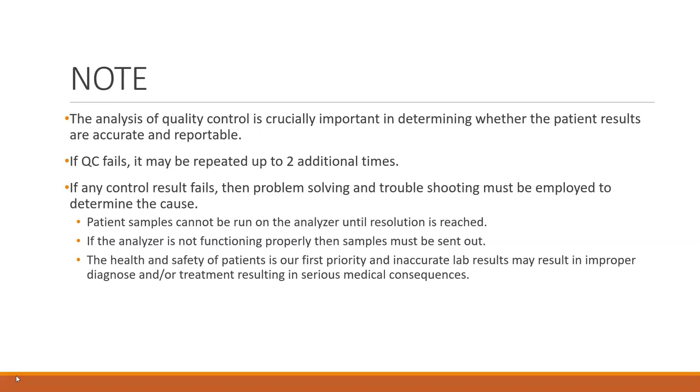What had happened was this person did not follow protocol, and the analyzer was not draining properly, so every result was more dilute than the previous result, which ended up with totally inaccurate results for the patient. I just want to let you know that this has consequences. That physician's practice had to pay for that emergency room visit because it was their fault.